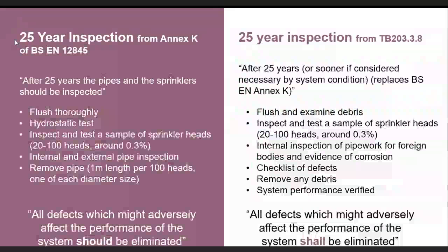This little slide is about the difference between Annex K and TB203. They are quite similar, but it's the language that's used. For example, in Annex K it says it should be inspected, and in TB203 it says it shall be inspected. Another key difference is that Annex K calls for a hydrostatic test. It means Annex K is encouraging increasing the pressure within all of the pipework to, I think, 15 bar or 18 bar, or 1.5 times the maximum working pressure, something like that, to check for condition. That is not there in TB203.